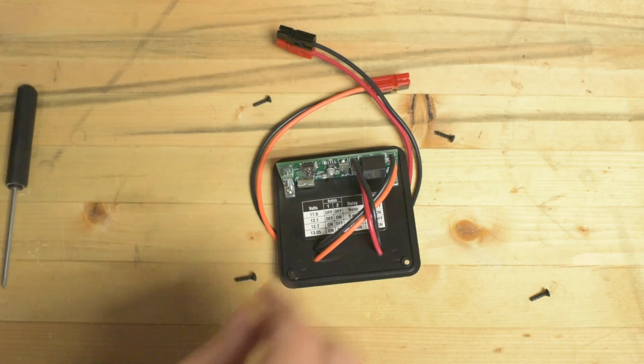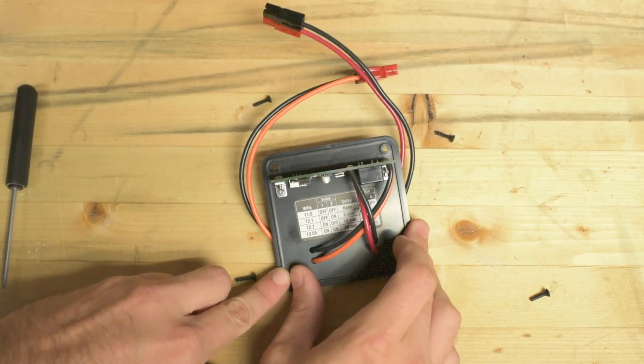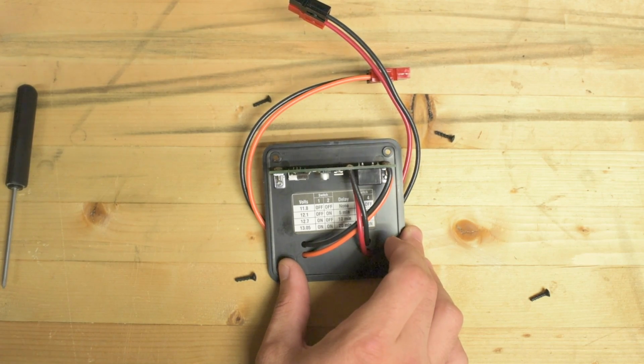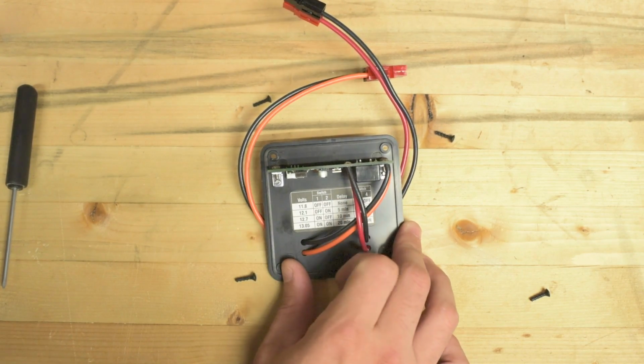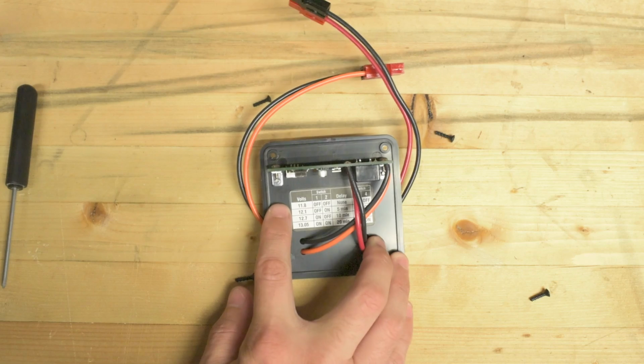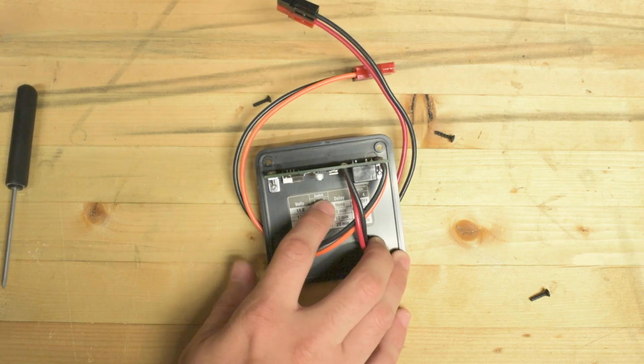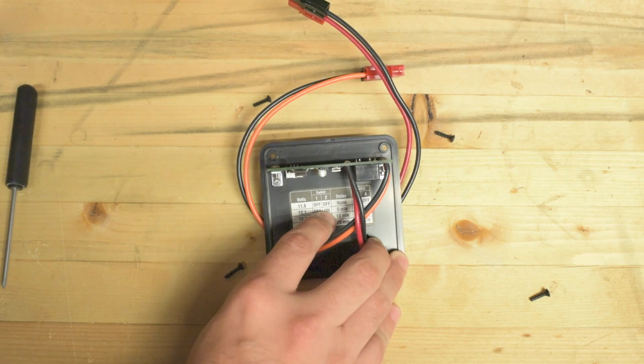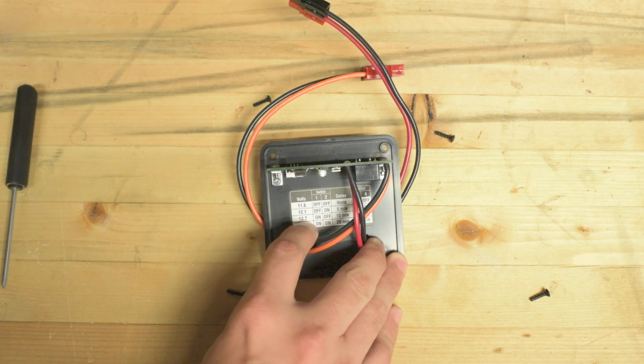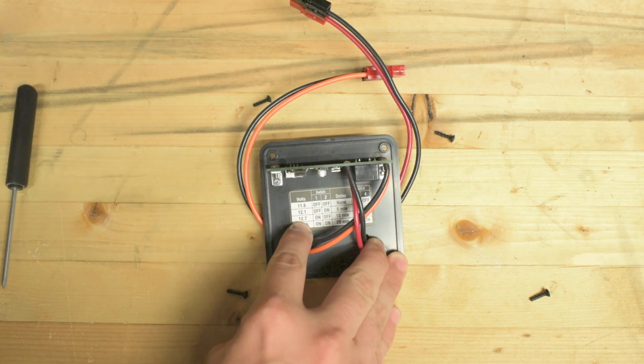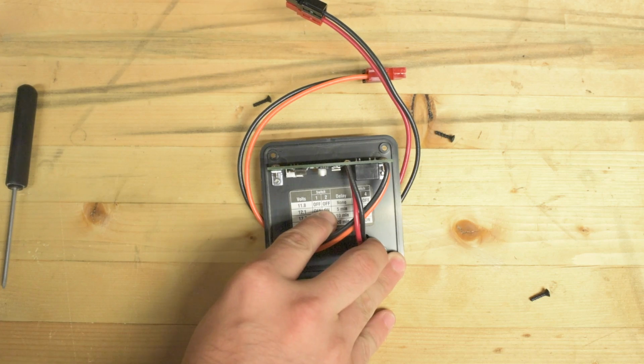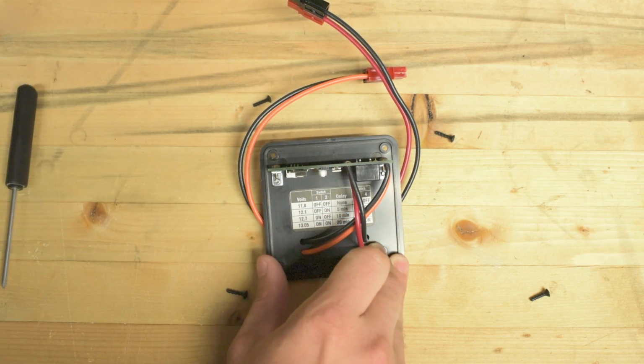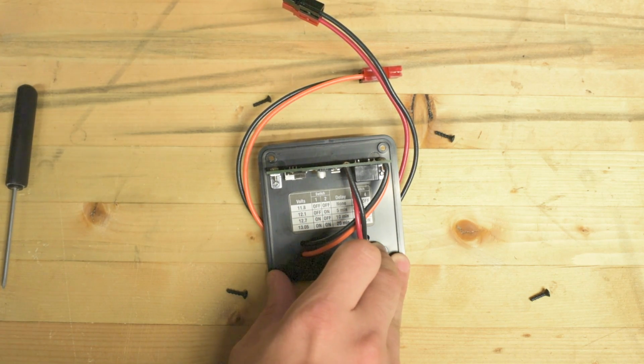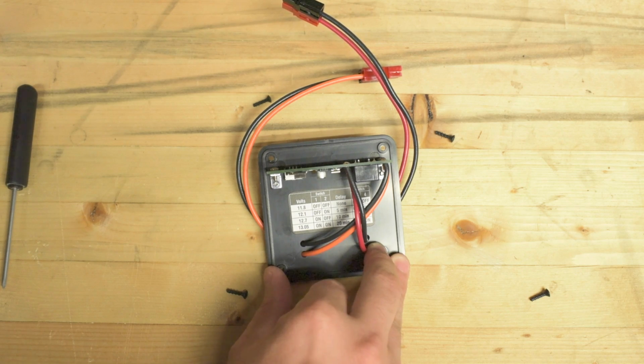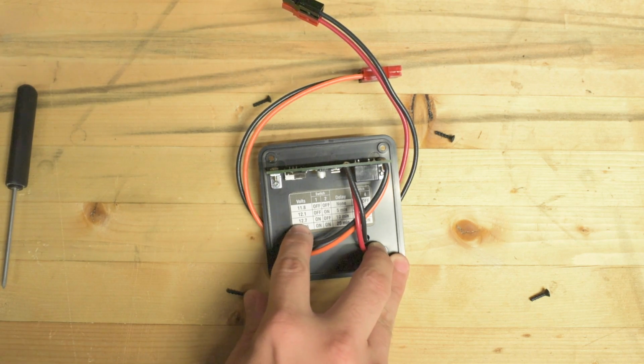So you can see in here, I'm not sure how legible that is, but there's a chart that lists the voltage set point and also the delay. I've got my delay set to 10 minutes, so once it goes below 12.7 volts, it'll wait 10 minutes — that takes care of hysteresis, like if you just get a load spike that draws the voltage down. It has to consistently be below 12.7 volts in order for it to shut off.